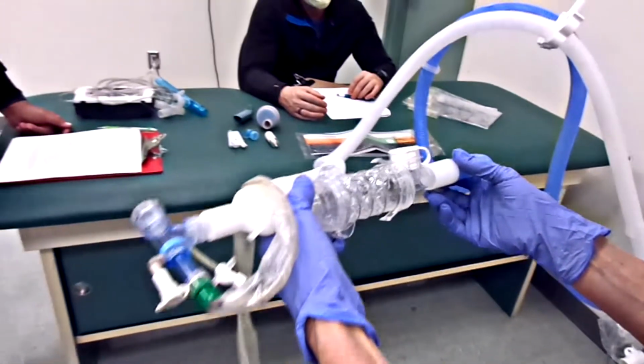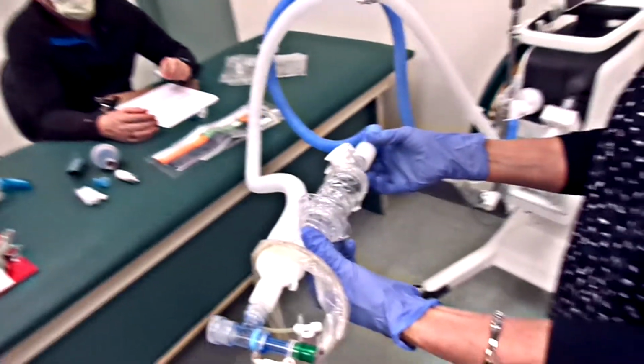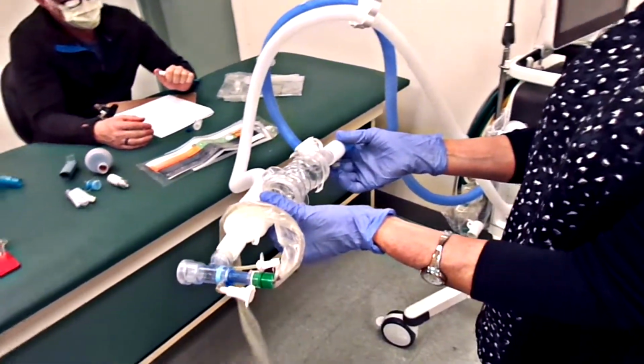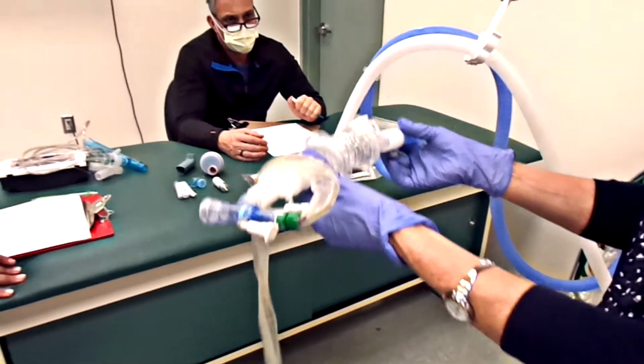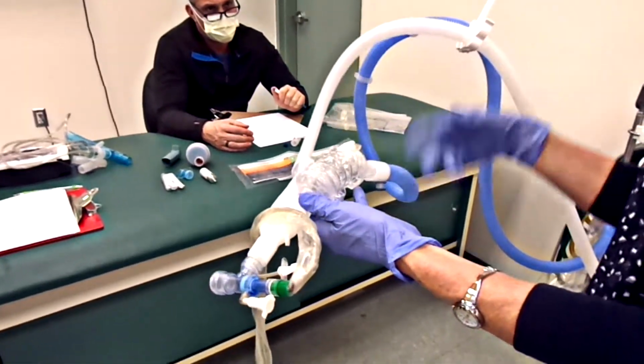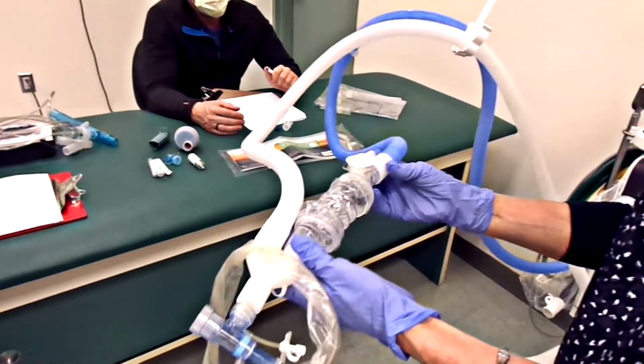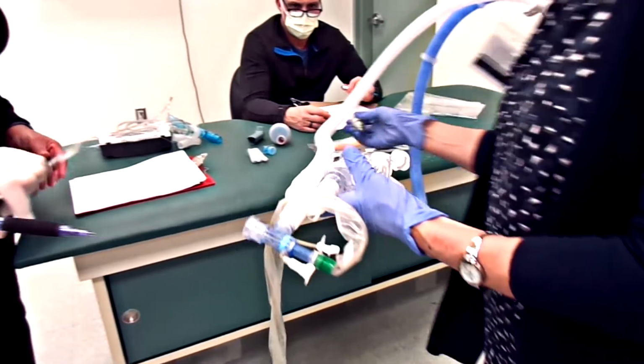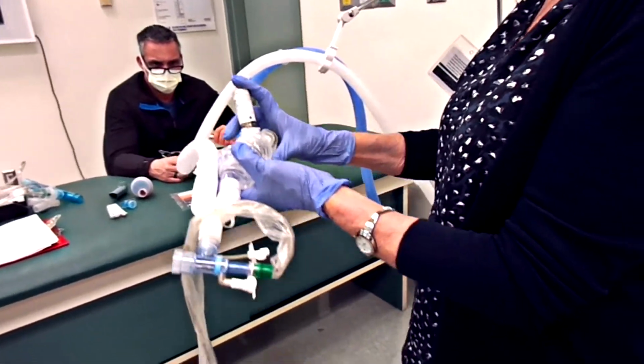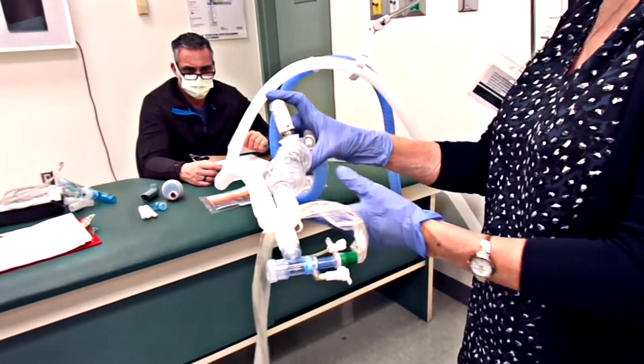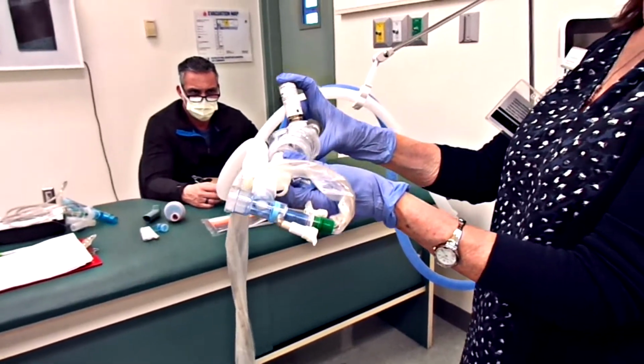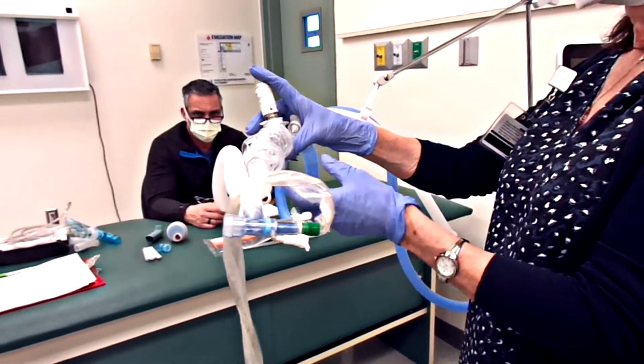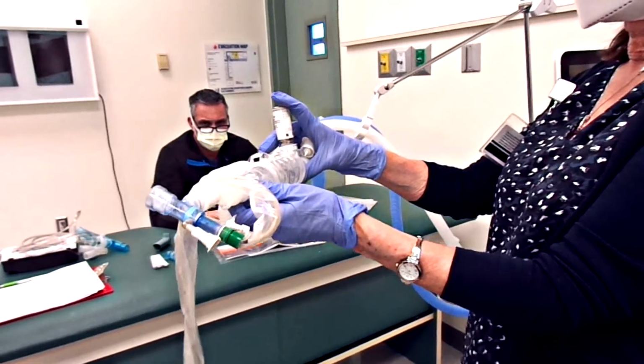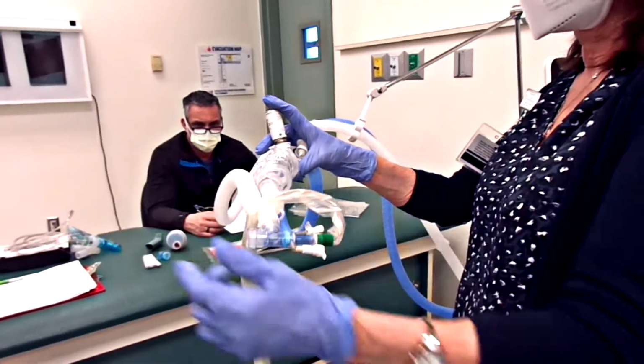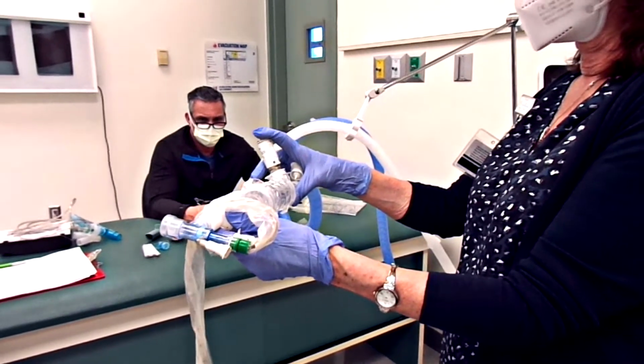On the inspiratory side, it will get delivered. Typically, MDIs get ordered when a patient's getting ready to go home. If they're going home on the ventilator and the family's going to be doing it, it's usually an MDI that goes in line with the circuit. And so you would just wait for the ventilator to deliver the inspiratory breath. So when you hear it start to go in, you just press. The medication gets suspended in the air and then it travels to the patient. Okay.